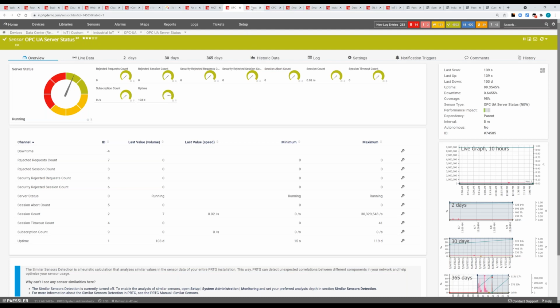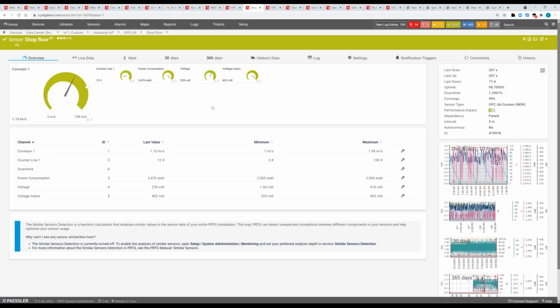Let's go a little bit further on the shop floor. We also integrated an OPC UA custom sensor, and this custom sensor can really connect to any node ID in the OPC UA namespace. You just have to define the node ID, and then we can pull the data. In this example, we have 5 metrics available, and I brought an example from the shop floor, like the speed of a conveyor, a count of a production line, power consumption, voltage mains. So you can really retrieve the data from your OT environment. You don't need a gateway, because PRTG supports OPC UA.